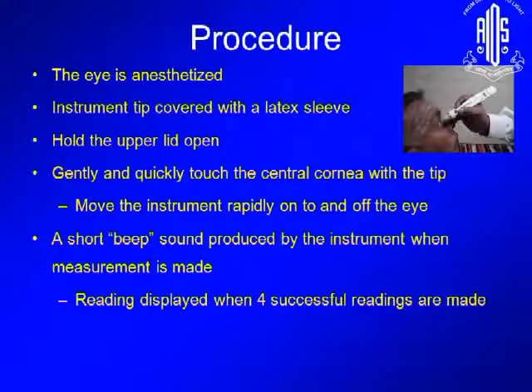So basically, you need anesthesia. The tip is covered with a latex sleeve. You hold the lid open and you rapidly applanate using this on the central cornea. A short beep is produced by the instrument when your measurement is made. For the Tono-Pen XL, the older model, you need 4 reliable measurements before it gives you a beep. For the Avia, it requires 10 measurements before it gives you the beep. And this is essentially how it's done.